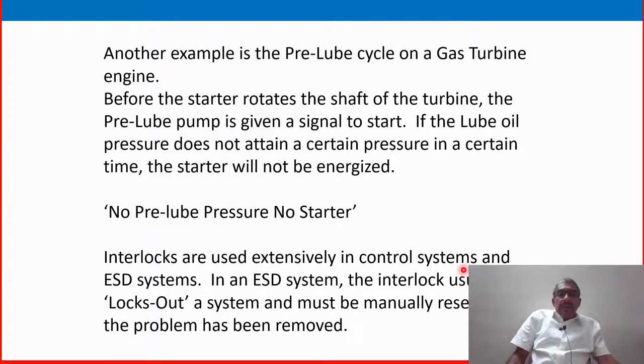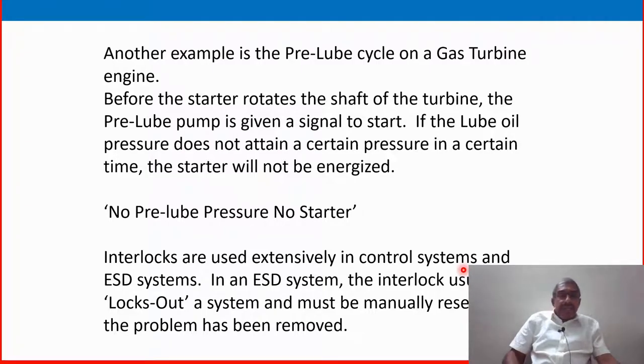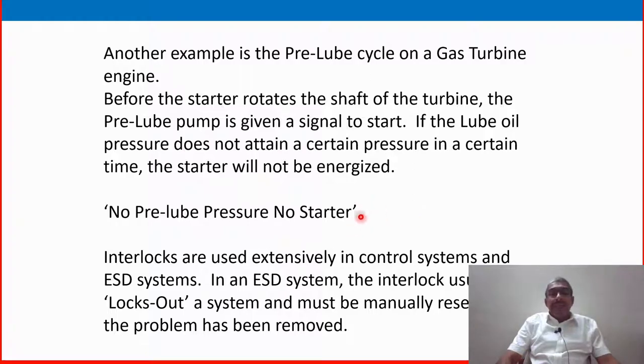Another example is the pre-lube cycle on a gas turbine engine. Before the starter rotates the shaft of the turbine, the pre-lube pump is given a signal to start. If the lube oil pressure does not attain a certain pressure within a certain time, the starter will not be energized. That means no pre-lube pressure, no starter. That is the concept — the interlocking mechanism working properly.